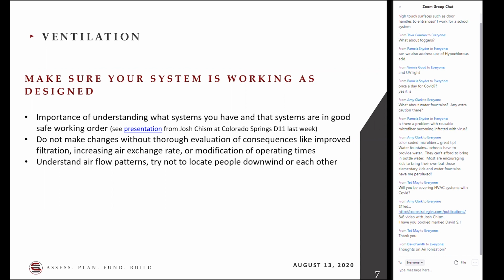If you have a building automation system, it could be a problem if somebody's sitting there looking at a computer screen and they say everything's working, but there's a linkage broke. So the motor worked, but the damper didn't move. I think I might have a picture that you've got in there that can show how you can unintentionally fool a thermostat.